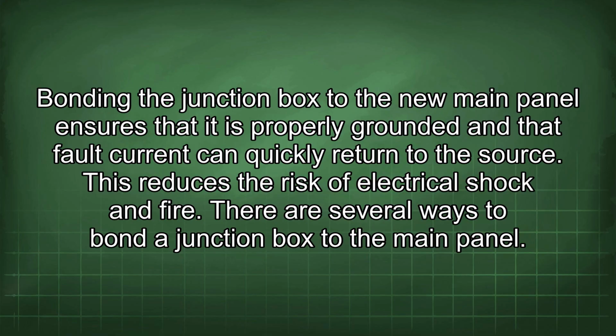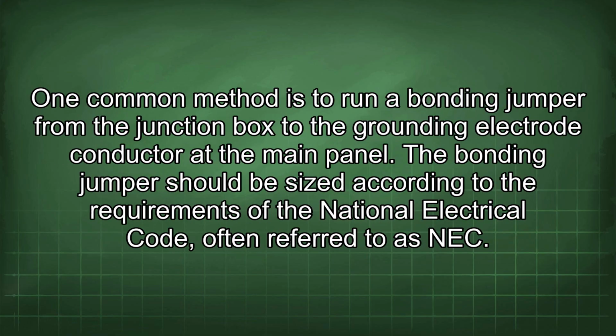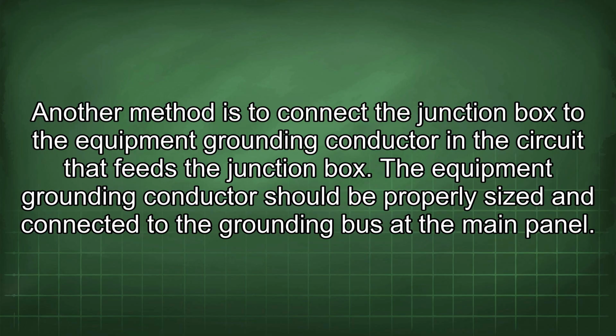There are several ways to bond a junction box to the main panel. One common method is to run a bonding jumper from the junction box to the grounding electrode conductor at the main panel. The bonding jumper should be sized according to the requirements of the National Electrical Code, often referred to as NEC. Another method is to connect the junction box to the equipment grounding conductor in the circuit that feeds the junction box. The equipment grounding conductor should be properly sized and connected to the grounding bus at the main panel.